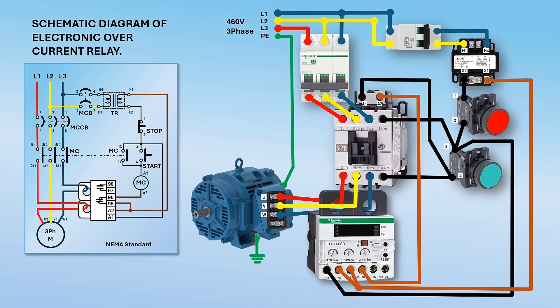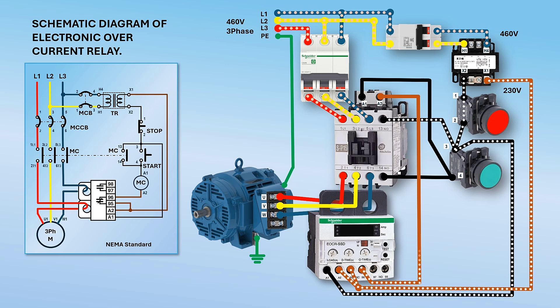Pay attention to the diagram as it changes status during the operation sequence. With 460 volts three-phase present on the upstream of the MCCB and MCB: switching on the MCCB makes voltage present on the contactor input. Switching on the MCB energizes the control transformer, stepping down the voltage from 460 to 230 volts, which is supplied to the control circuits. The closed loop of transformer output, NC of stop button, and EOCR terminals A1 and A2 energizes the protection relay.